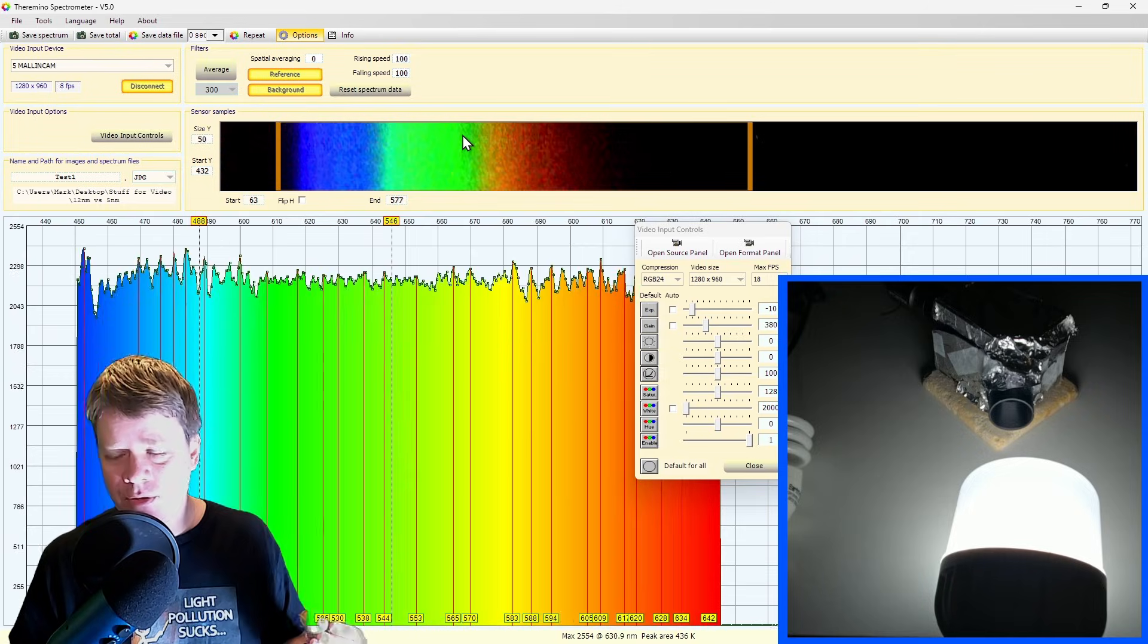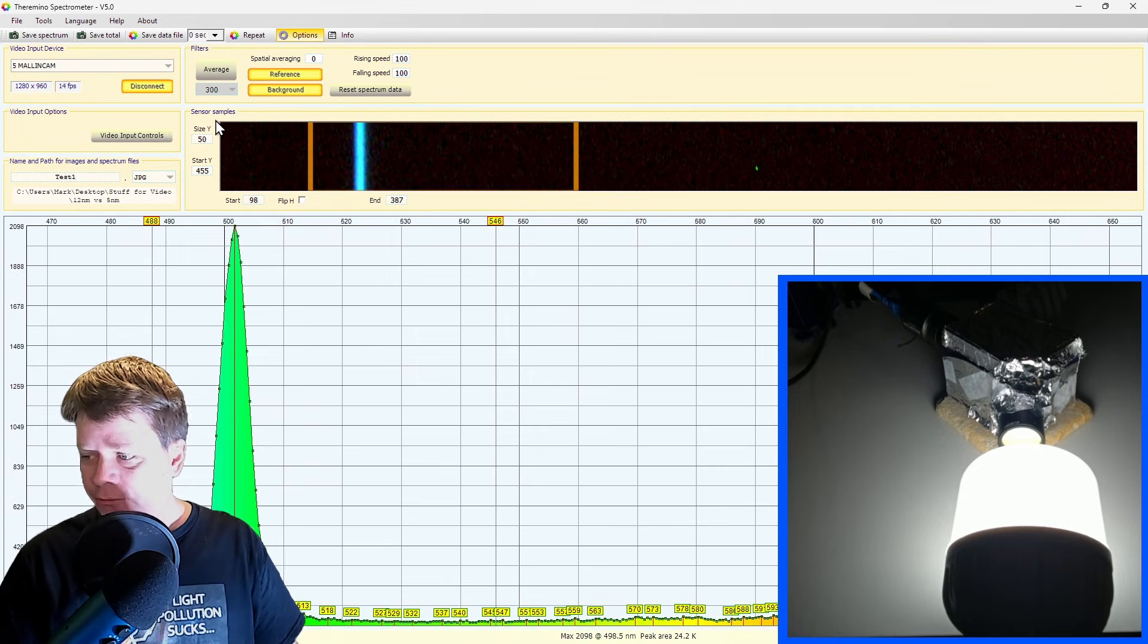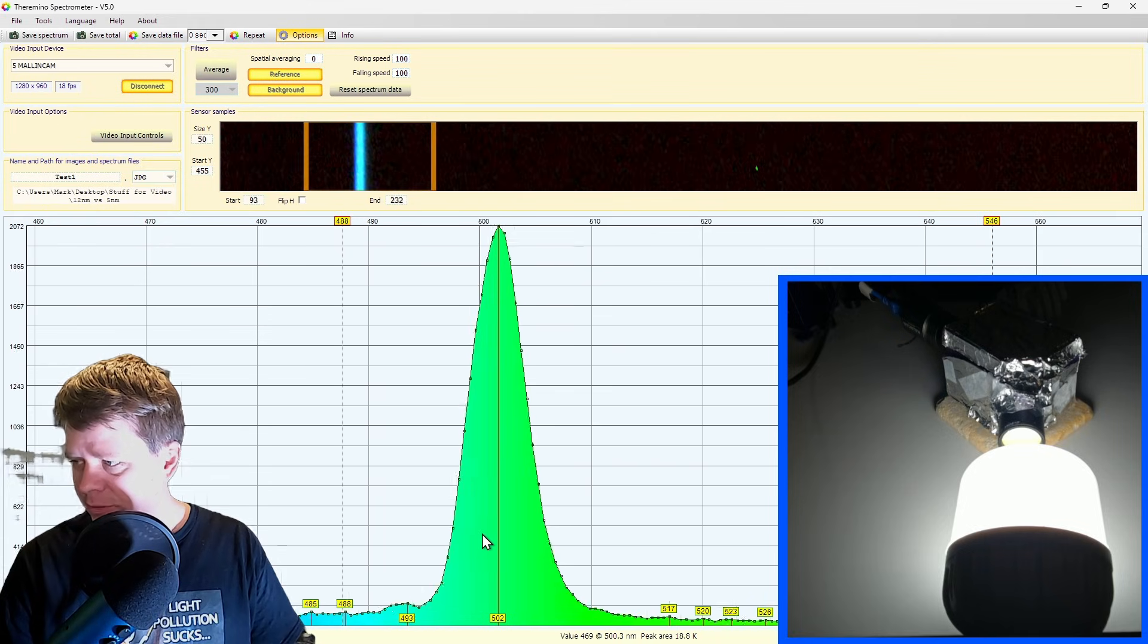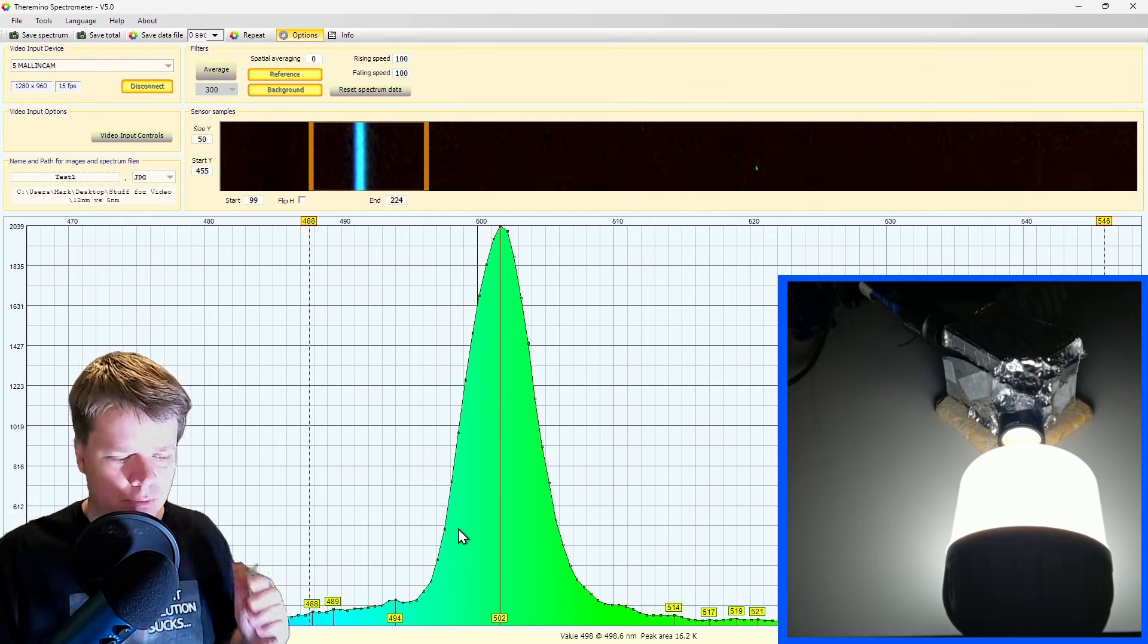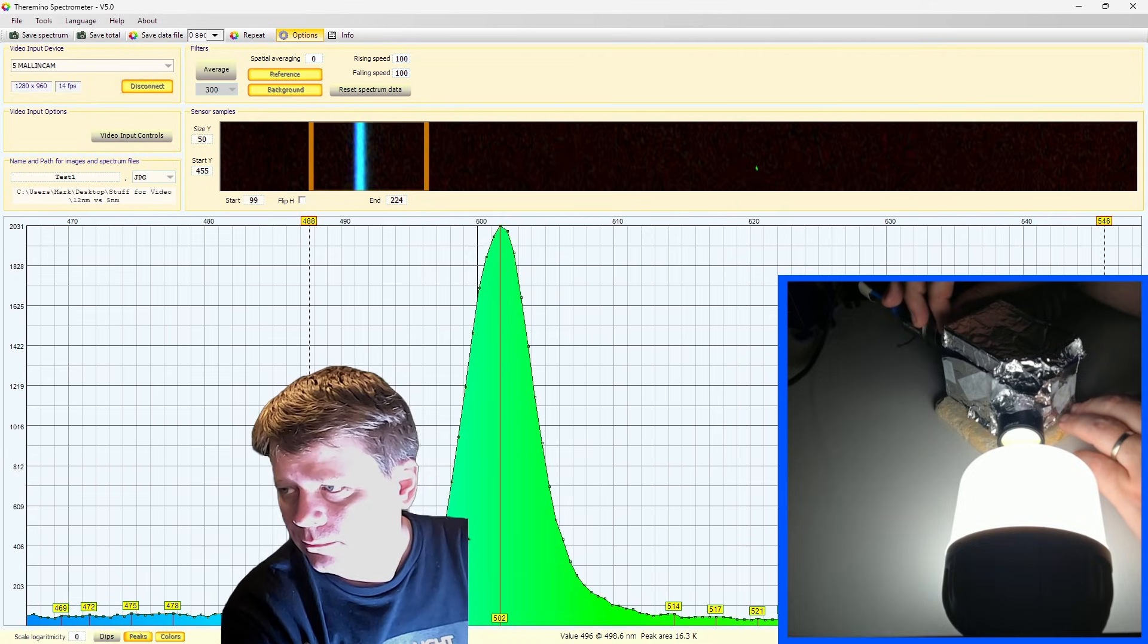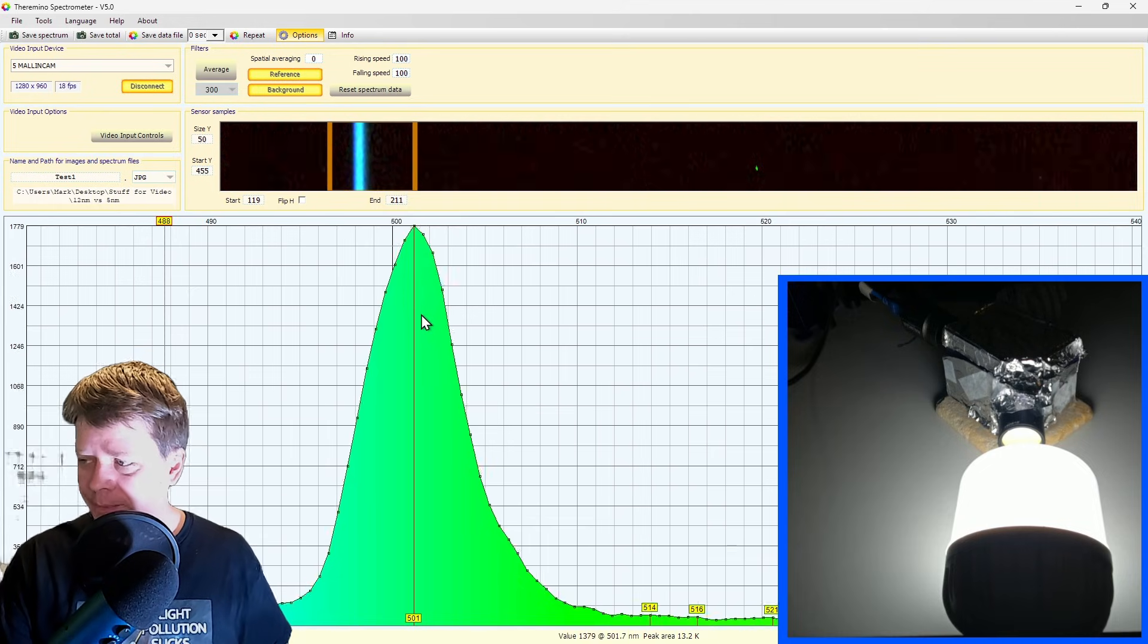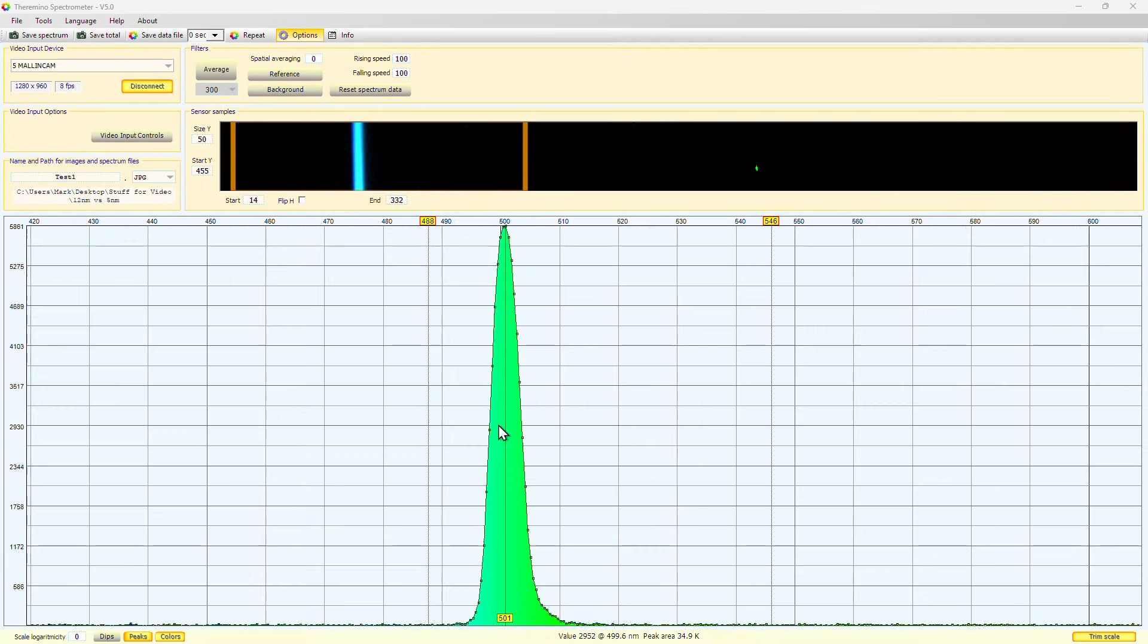So the center of this filter should be around 500 nanometers. We've done calibration. Look at that. We're already at around 500 nanometers. So we probably need to focus this a little bit more because we need to focus at each part of the wavelength that we're looking at to get the best measurement. So I'm going to go ahead and do that right now. So it looks like we've got it in focus. The peak is right around where it should be.